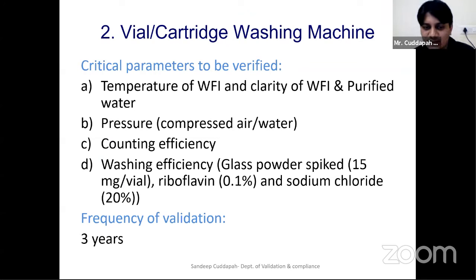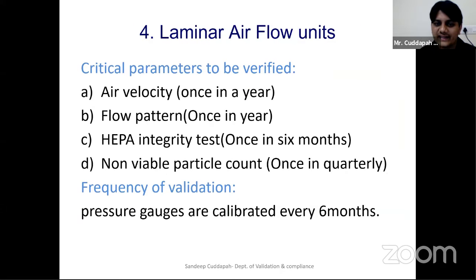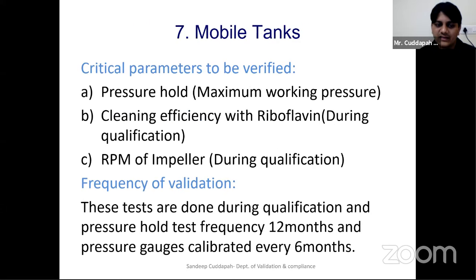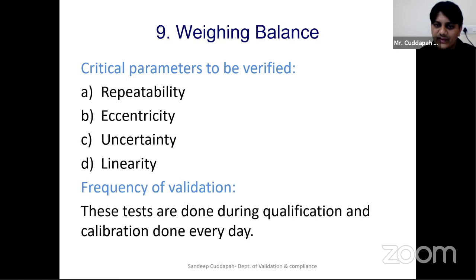You will decide what range it can be maintained in. So as I told you, in the same way, for each equipment you can identify what are all the critical parameters and at what frequency you have to validate those equipments. So this weighing balance will be very useful to you. You will normally use a weighing balance even in your lab also. So in case of a weighing balance, you can do these tests: you can verify repeatability, eccentricity, uncertainty, and linearity. These are the tests normally done during weighing balance qualification.